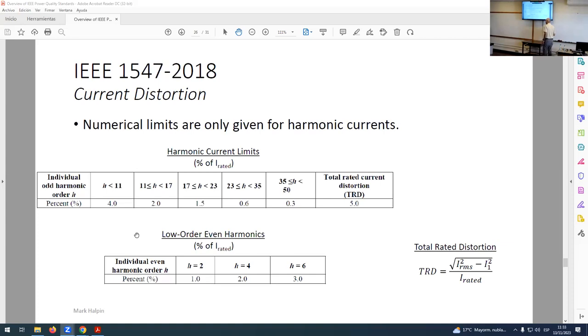So, to recognize this potential sensitivity of inverters to imperfections in the interconnecting voltage, we relaxed the even order harmonic limits just a little bit. If you look at this row in 519, the even order harmonics are limited to 25% of these. For the second harmonic we're keeping it at 25%, but for the fourth harmonic it's 50%, and for the sixth harmonic, 75%. And again, that came not from us in the utility arena, but from the power electronics manufacturing community. Those were recommendations and things they wanted, so that's where that came from. But in general, this is very similar to 519. This is the most restrictive row.